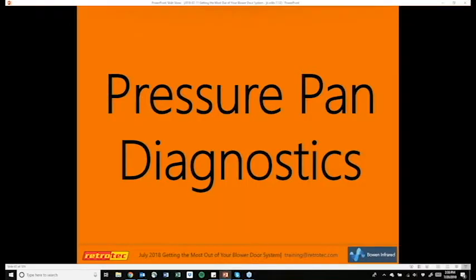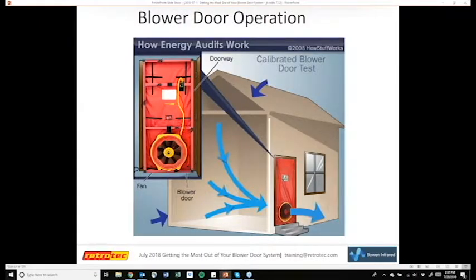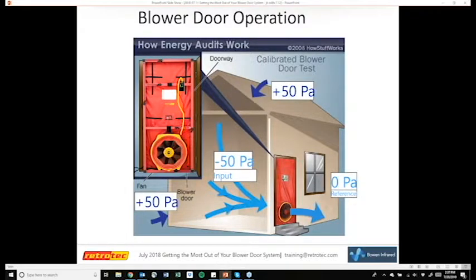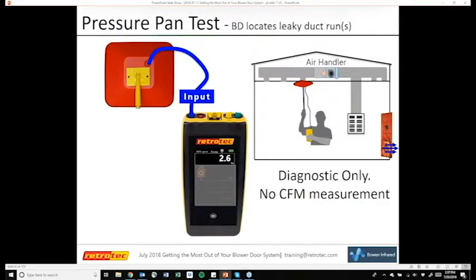So pressure pan diagnostics is another way to pinpoint where leaks are coming from. With the pressure pan, in a similar way, you depressurize the house to 50 Pascal if you were going to test it. Then you attach your pressure pan to your gauge. If you're using the Retrotec gauge, you would attach it to the blue port. With your blower door running at 50, there's not really a specific number you're looking for here. You just want to see if the leaks exist. So for example, if you're trying to find duct leakage with your blower door, you can depressurize the house, go around with your pressure pan, and check supplies and returns to see if you're getting a big pressure differential between that and the indoor space.